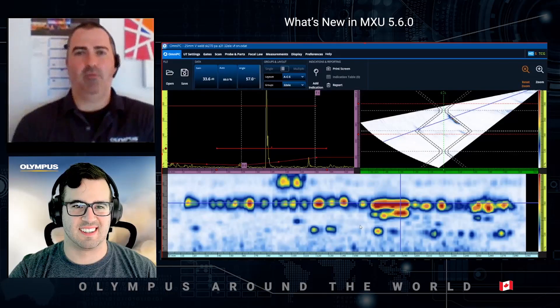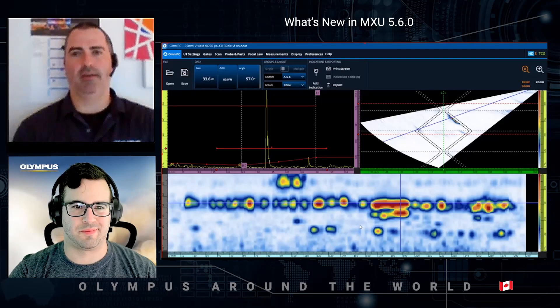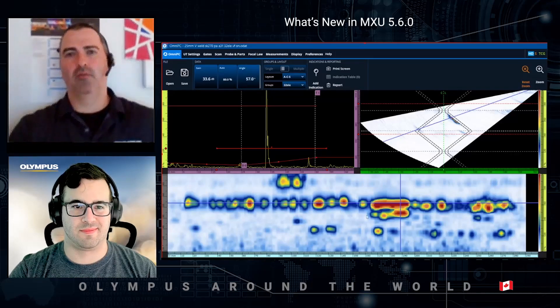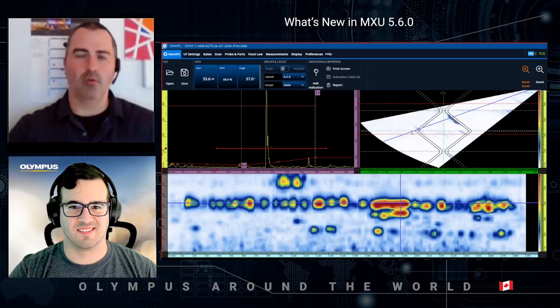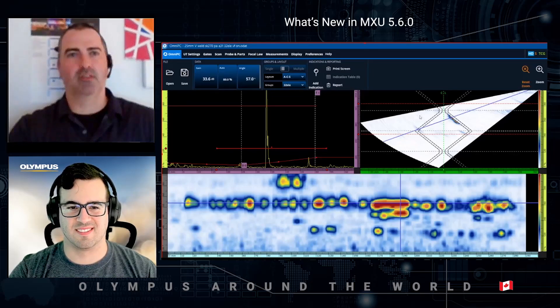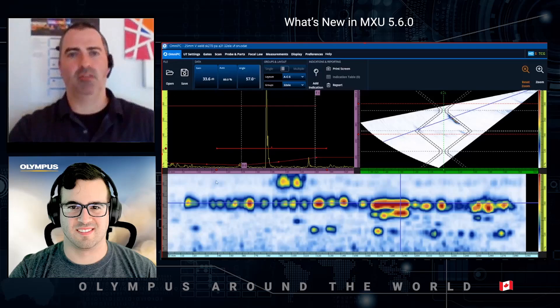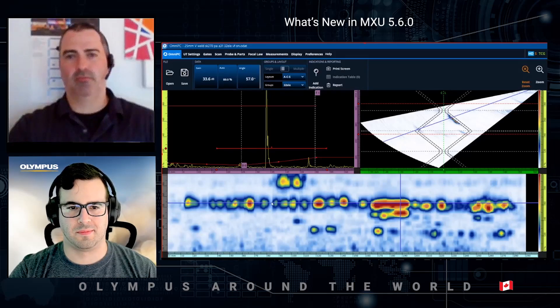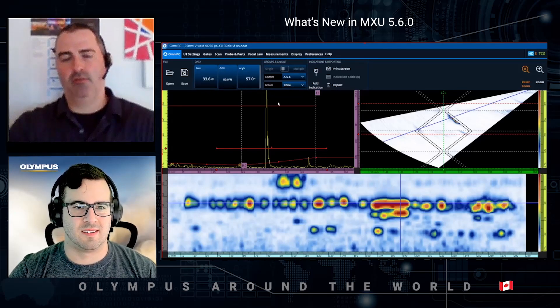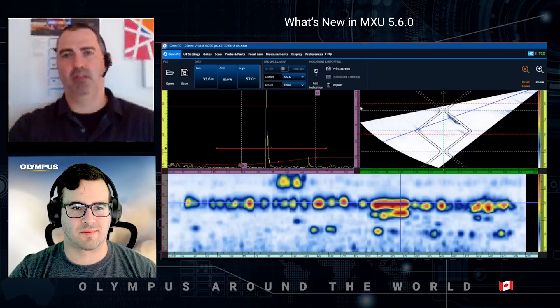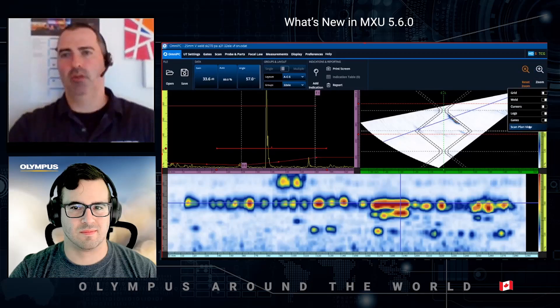Moving on to the next item: the configuration and adjustment of the weld overlay, as seen during the acquisition or analysis process. I'm currently using OmniPC 5.6 with a sample data file — a simple coupon with a sample weld in the middle. Prior to 5.6, there was basically no way of reviewing the scan plan. Now if you go under View, you have the new Scan Plan View available in OmniPC.